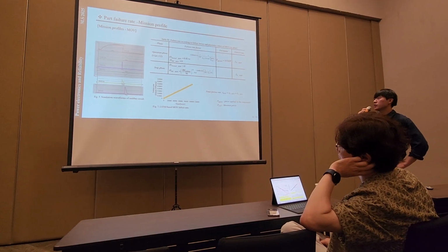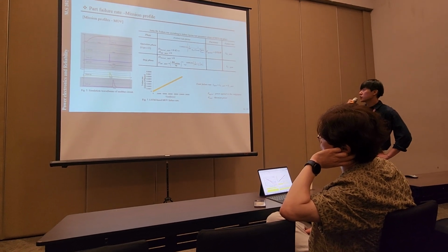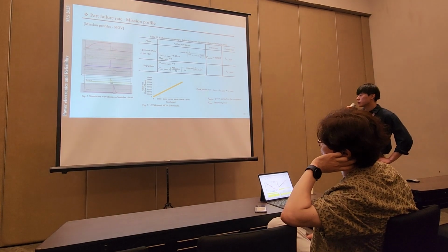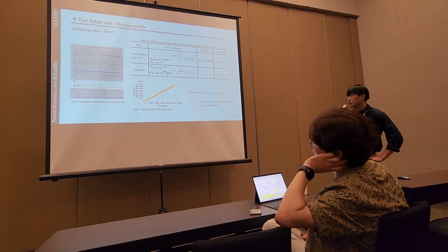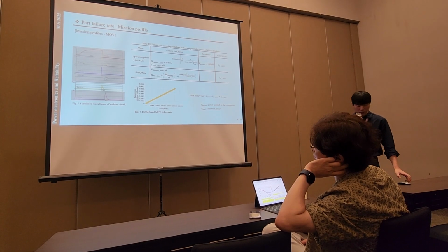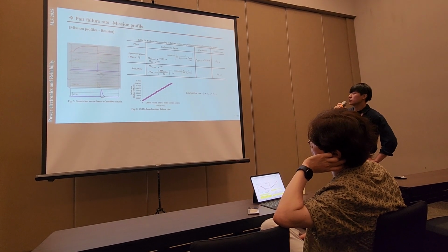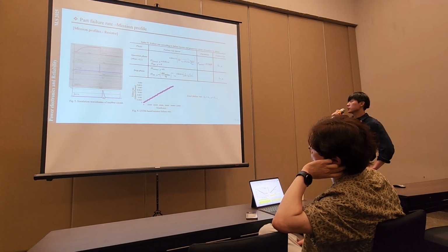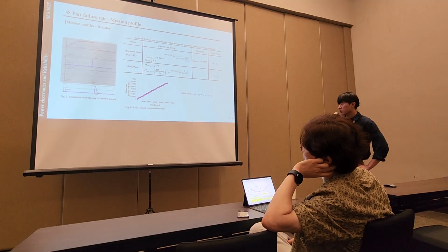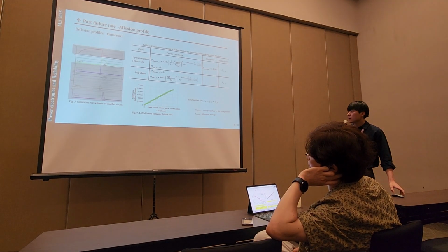Next page is for the MOV mission profile. The main parameter of the MOV thermal factor is the power ratio between applied power and rated power. Figure 7 shows the MOV time-dependent failure rate. Next is for the resistor mission profile. The main parameter of the resistor thermal factor is also the power ratio. Figure 8 shows the resistor time-dependent failure rate.